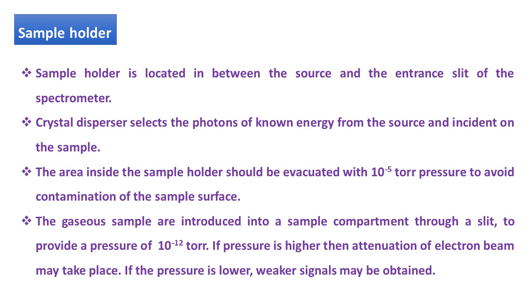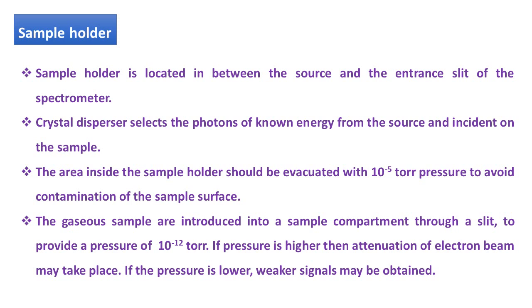If pressure is higher, then attenuation of electron beam may take place. And if the pressure is lower, weaker signal may be obtained. So generally in sample holder, high vacuum is required in XPS.